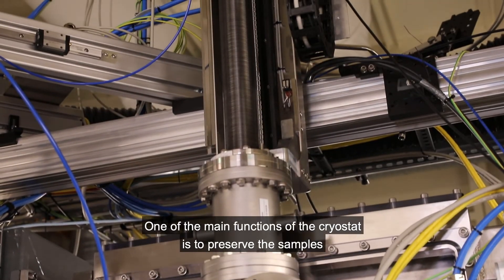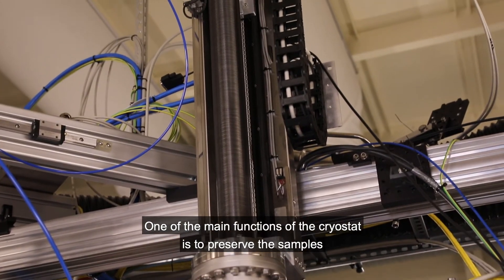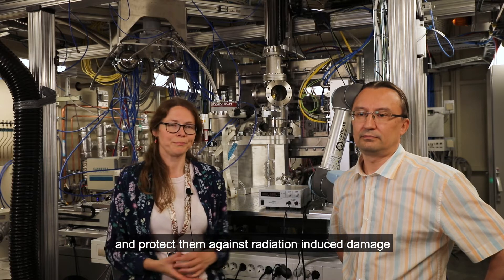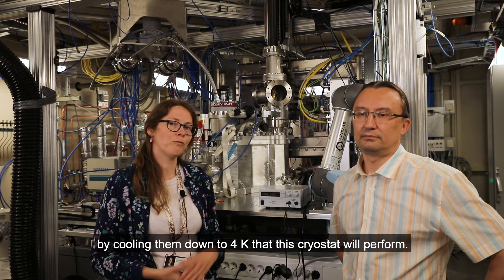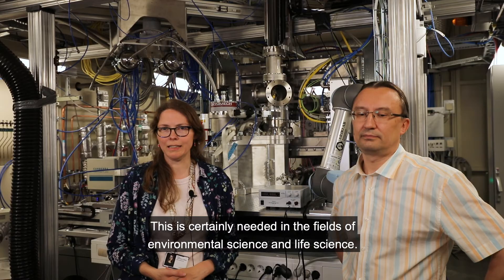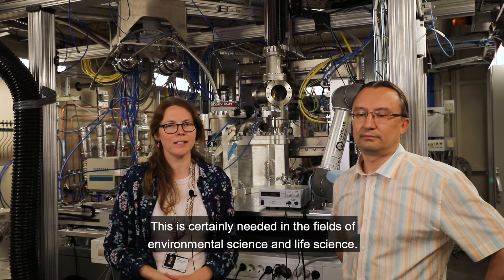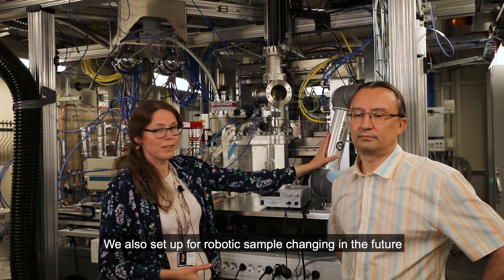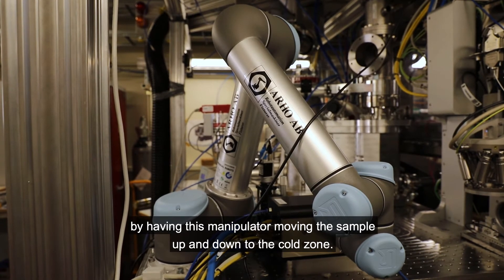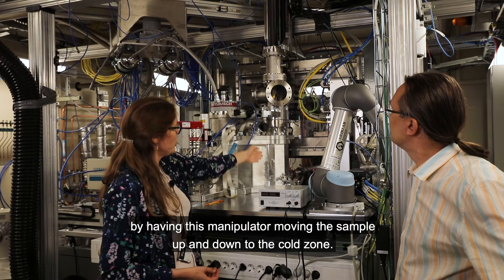One of the main functions of the cryostat is to preserve the samples and protect them against radiation-induced damage by cooling down to four Kelvin. This is certainly needed in the fields of environmental science and life science. We are also set up for robotic sample change in the future, by having this manipulator moving the sample up and down to the cold zone.